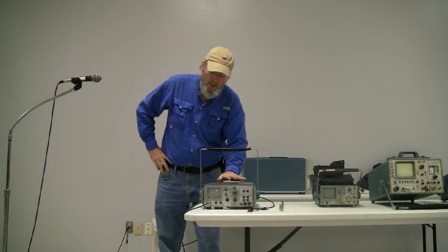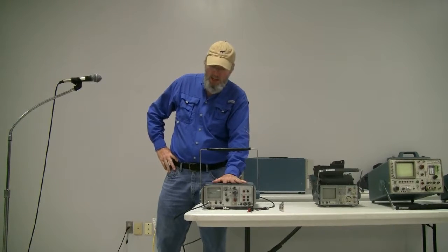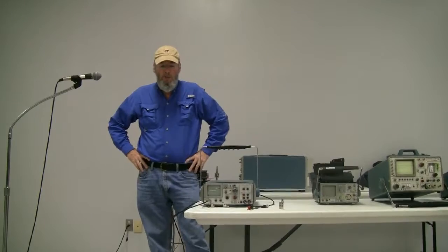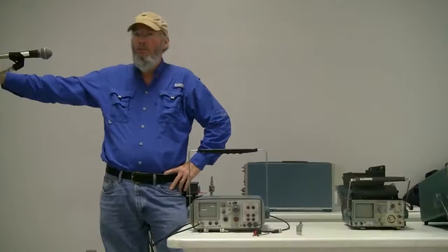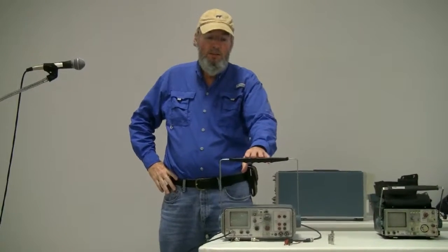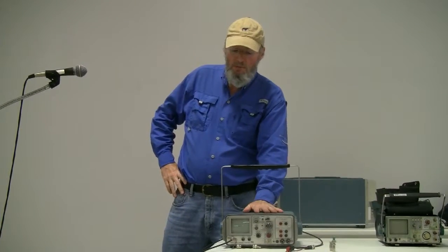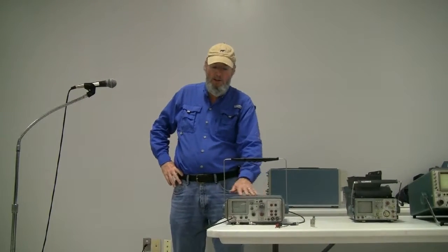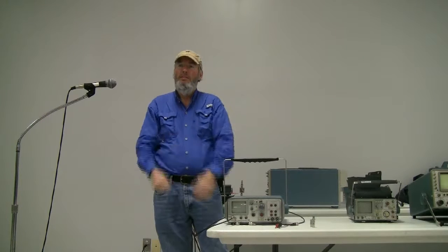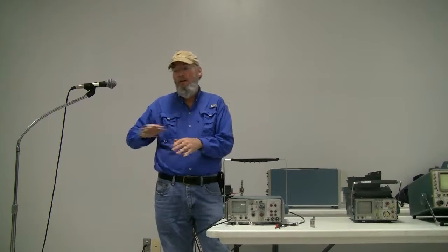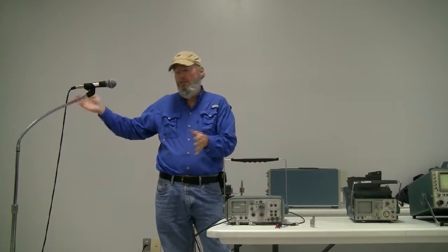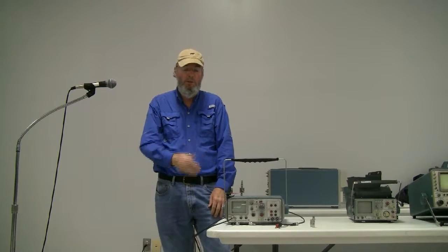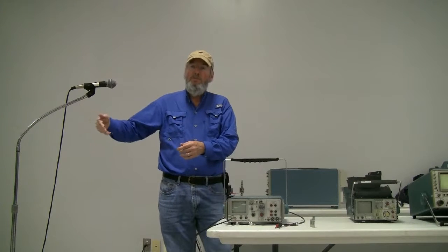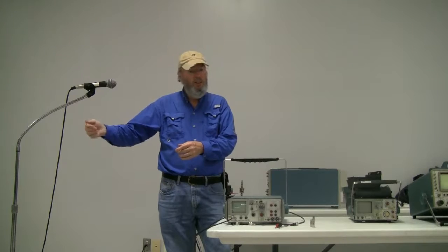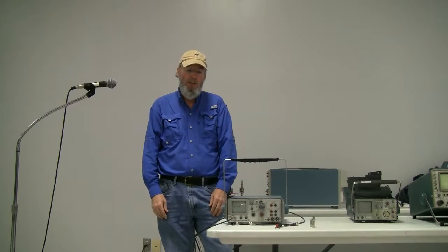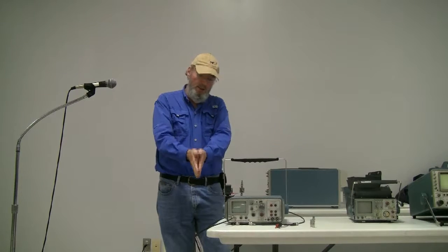There's a similar device that Tektronix actually built, same size and type, for the old Bell system, for looking down telephone wire pairs. This is a model 1502; that one's a model 1503. Instead of using a very fast step pulse like this one does with high resolution, it uses a half sine wave, because that'll travel down worse lines like twisted pairs, Romex, and similar cable, whereas the step pulse wouldn't work as well. So what we're going to do is hook that 1503 up at one of the poles and look down that buried Romex in the conduit. Once we calibrate, we should be able to see where the fault is.